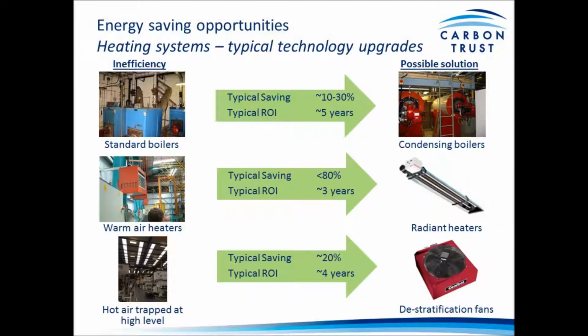If you are going to look to invest in plant upgrades for heating systems, there are many ways to do this, but these are some of the more common ways that we see and recommend as we go around and perform energy audits on buildings. So boilers used for heating have become much more efficient than some of their older counterparts, and this is largely due to stricter building regulations. And these regulations set minimum standards for new and replacement boilers. However, if you opt for an even higher level of efficiency, you could cut your energy bills by up to 30%. Condensing boilers are the most efficient designs that you can get, and typically all modern boilers are condensing.